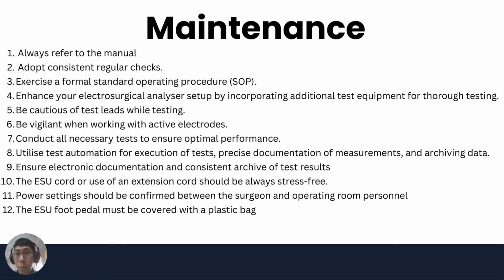Sixth, be vigilant when working with active electrodes. Avoid contact with the active electrode or return pad of the electrosurgical unit when it is activated in either cut or coagulation mode. Always switch off the ESU before adjusting or removing connections. Additionally, be vigilant of other flammable hazards in the vicinity. Conduct all necessary tests to ensure optimal performance.